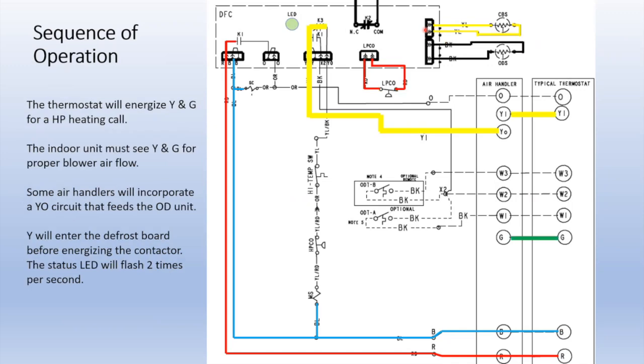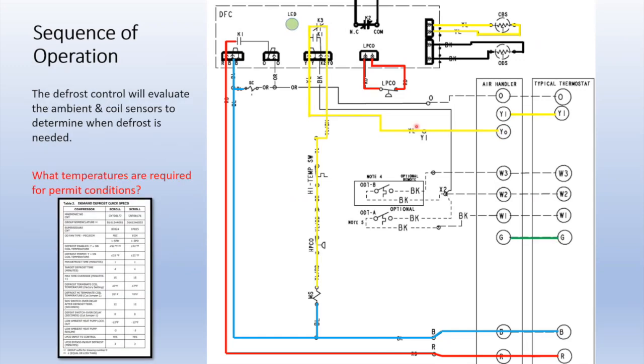So now we're going to give it a Y signal. So Y is going to come through here. It's going to go through the K3 relay, which is normally closed. That has the ability to intercept the Y signal before the contactor. It does have a 1 minute compressor on delay. If the compressor just shut off, it won't turn back on for another minute. So you can't do short cycles.